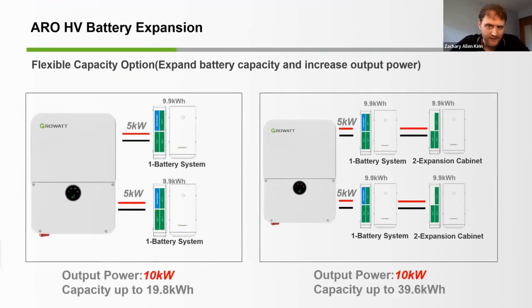The 2 ARO high voltage battery packs may be implemented in parallel in the picture shown on the left, right? So the inverter features 2 battery input terminals, and that allows for 2 separate ARO battery packs to interface with the MIN inverter to increase your capacity up to 19.8 kilowatt hours, as well as increase the output power up to 10 kilowatts.